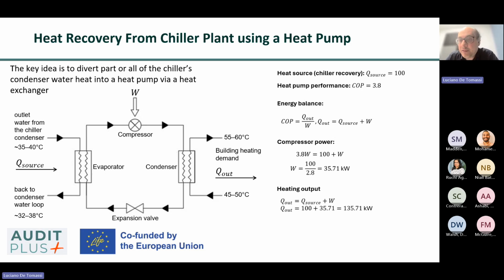A heat pump can be integrated with a chiller plant by connecting it directly into the condenser water loop, allowing waste heat from cooling processes to be upgraded and reused for useful heating within an industrial facility. The key principle is to divert part or all of the low-grade heat rejected by the chiller condenser into the evaporator side of a heat pump rather than rejecting it fully to a cooling tower or dry cooler.